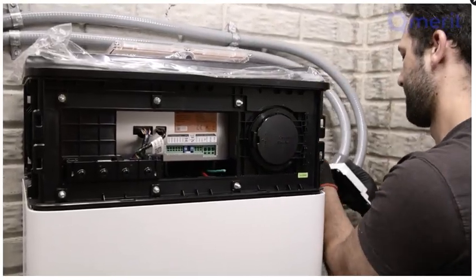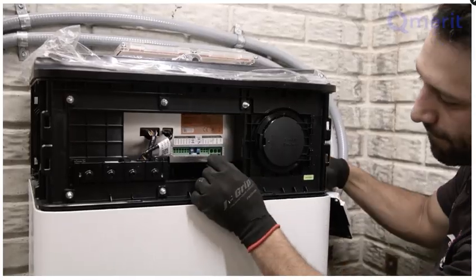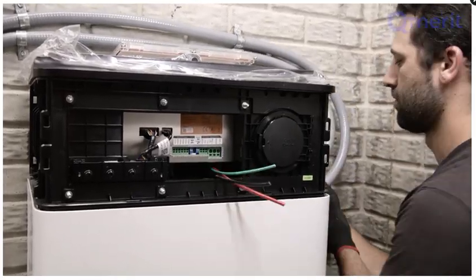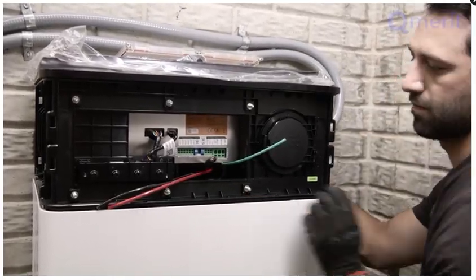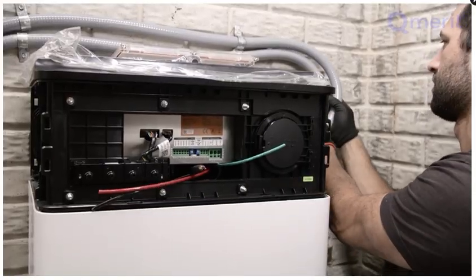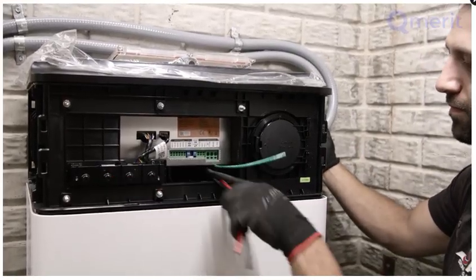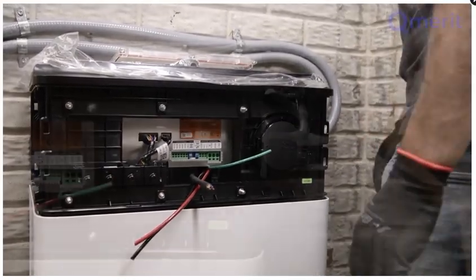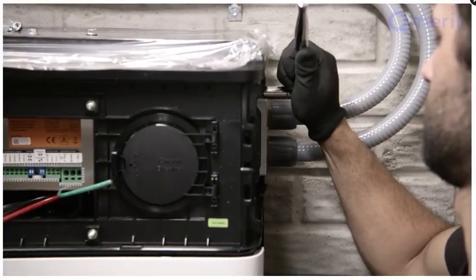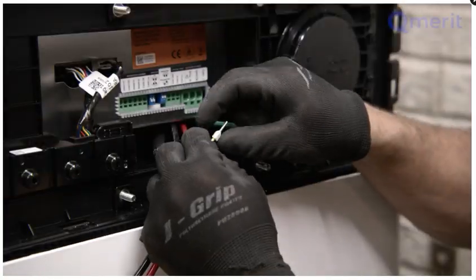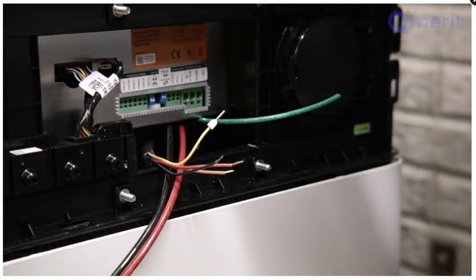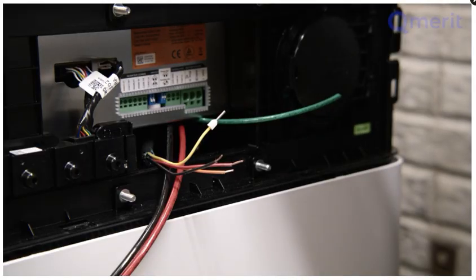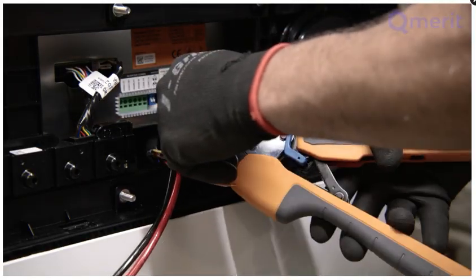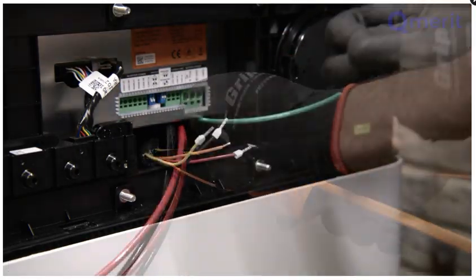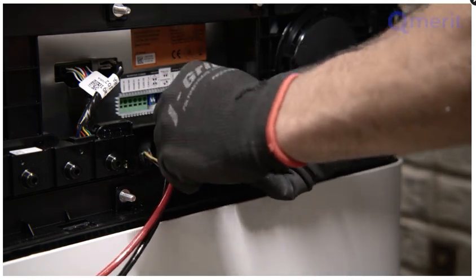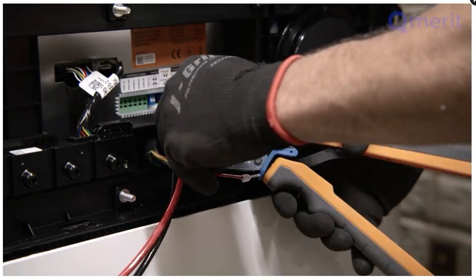After successfully running both the wires through the conduit, route them through the duct on the side before connecting the side seal cover. The wires will appear in the front of the BCU. You're now ready to connect them to the BCU. At this time, you can connect the side seal cover. Note, there are 2 sets of ferrule crimps provided. The orange ferrule crimps are for single, 22 gauge wire installation and the white ferrule crimps for twin wire installation or when using 18 gauge wire.